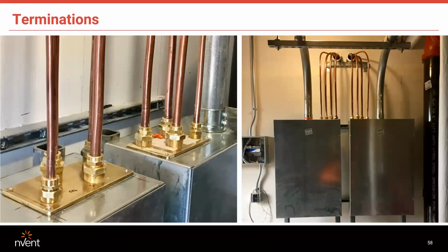So what the contractor does is cut a rectangular hole in the top of the box and bolt the brass plate to the box. The brass plates are tapped, so threaded glands will screw right into them. That would comply with the NEC's requirements. If by chance you're using one of our multi-conductor cables, no brass plate is required. Just use a regular lock nut and you'll be fine.